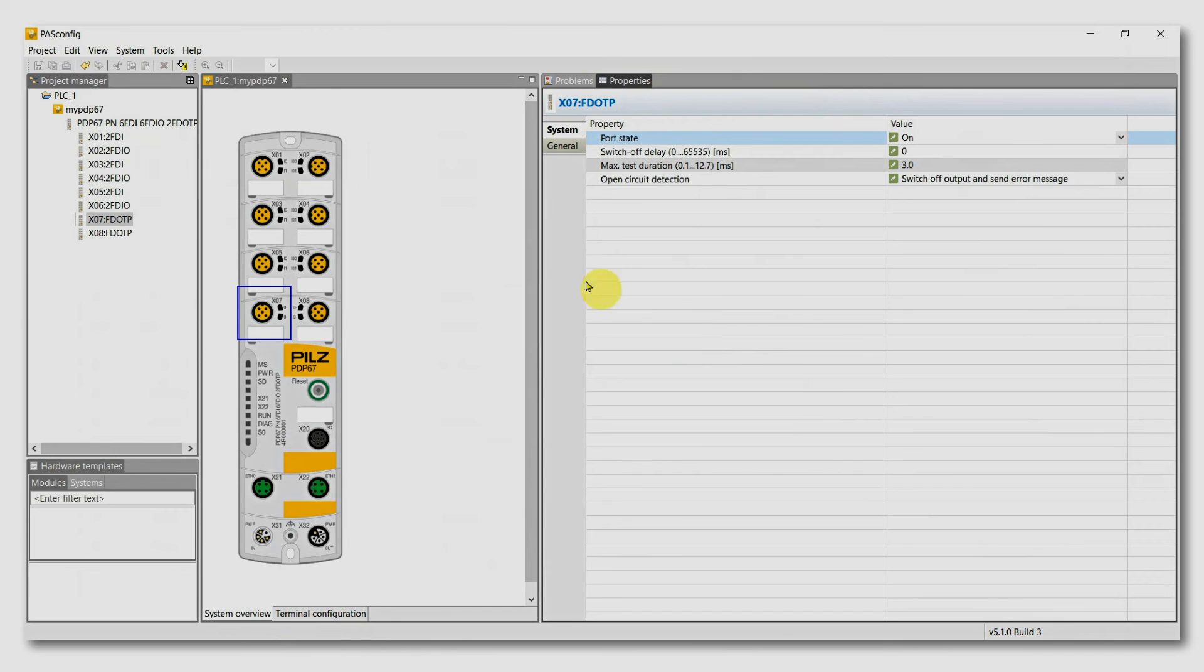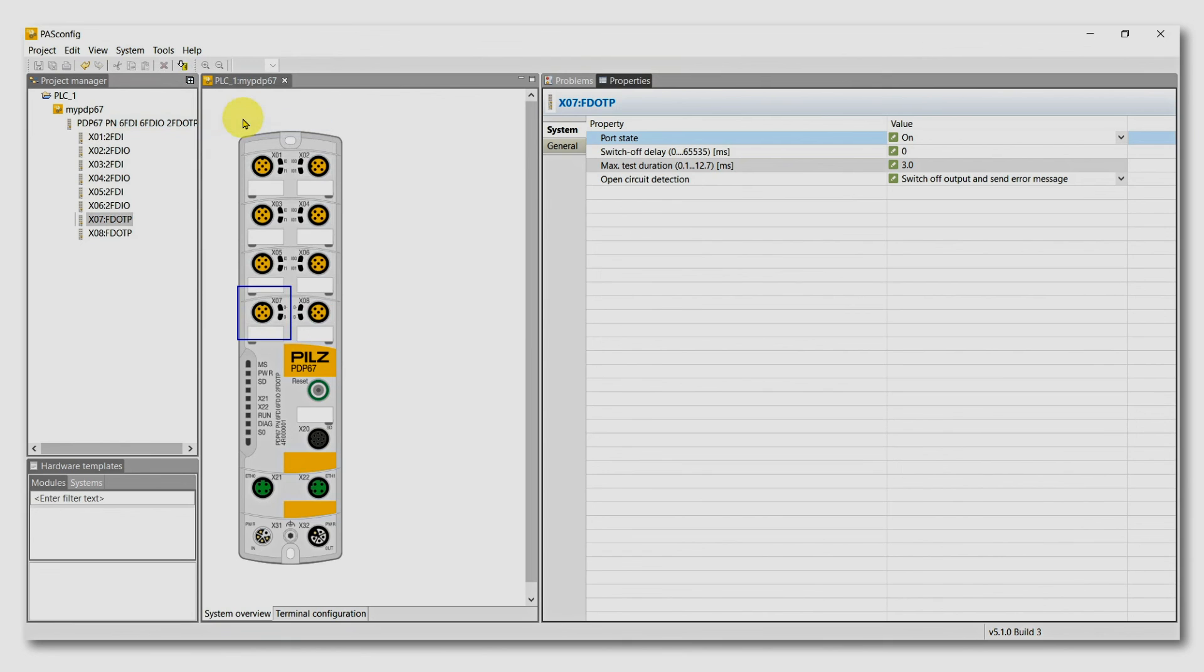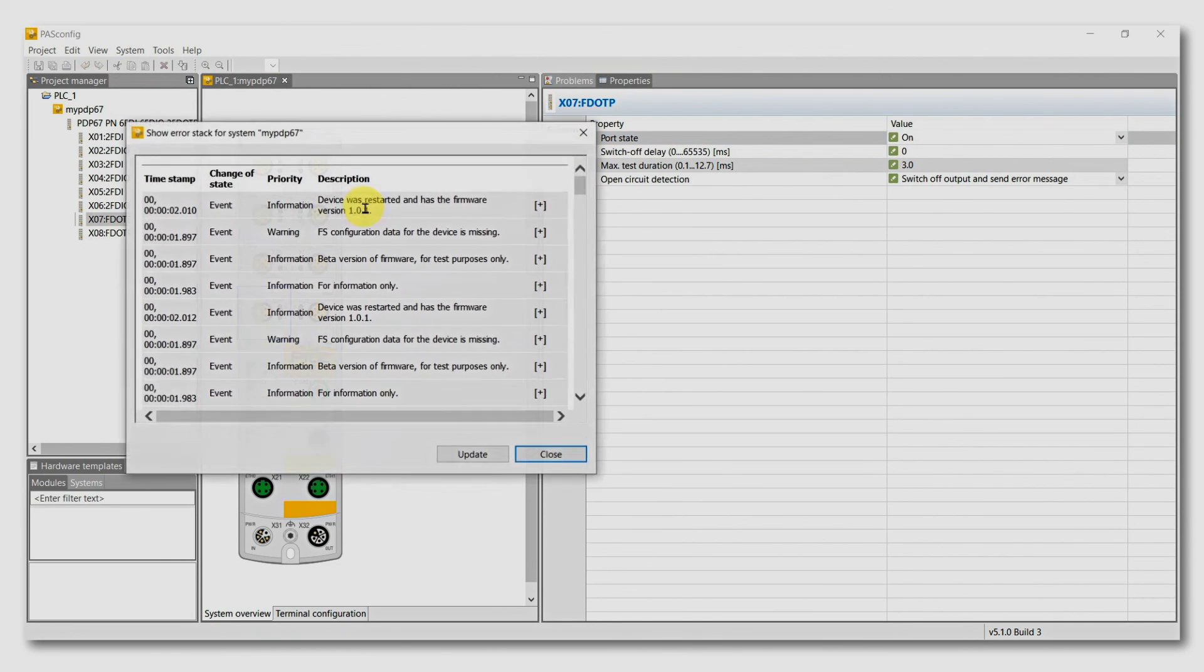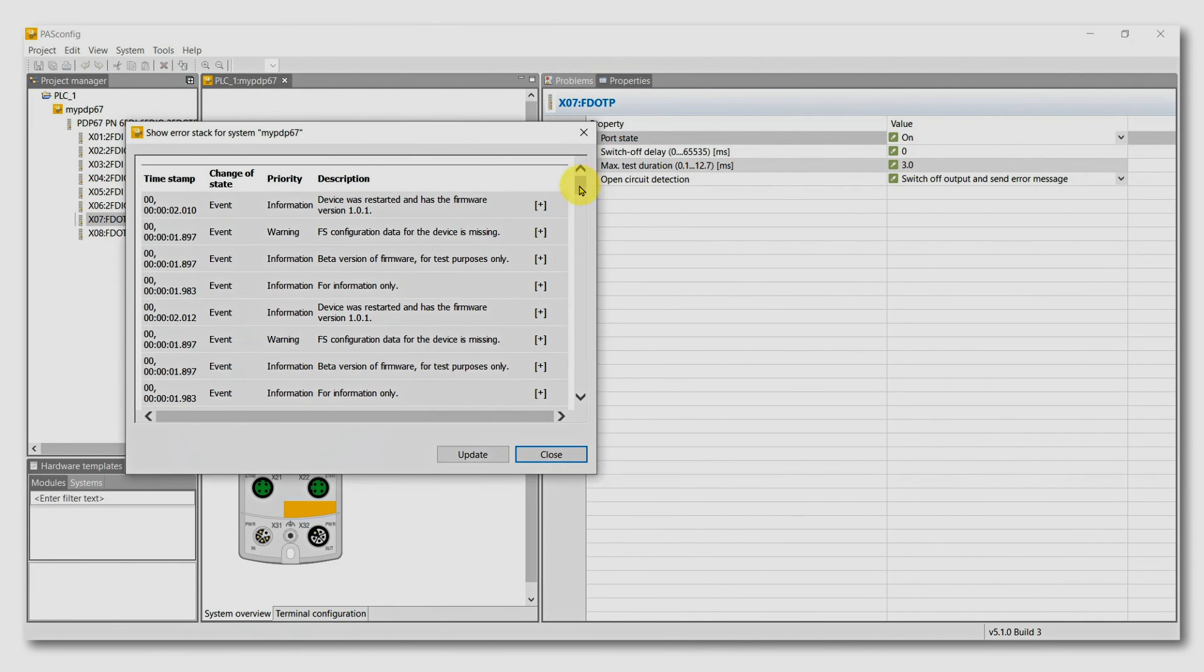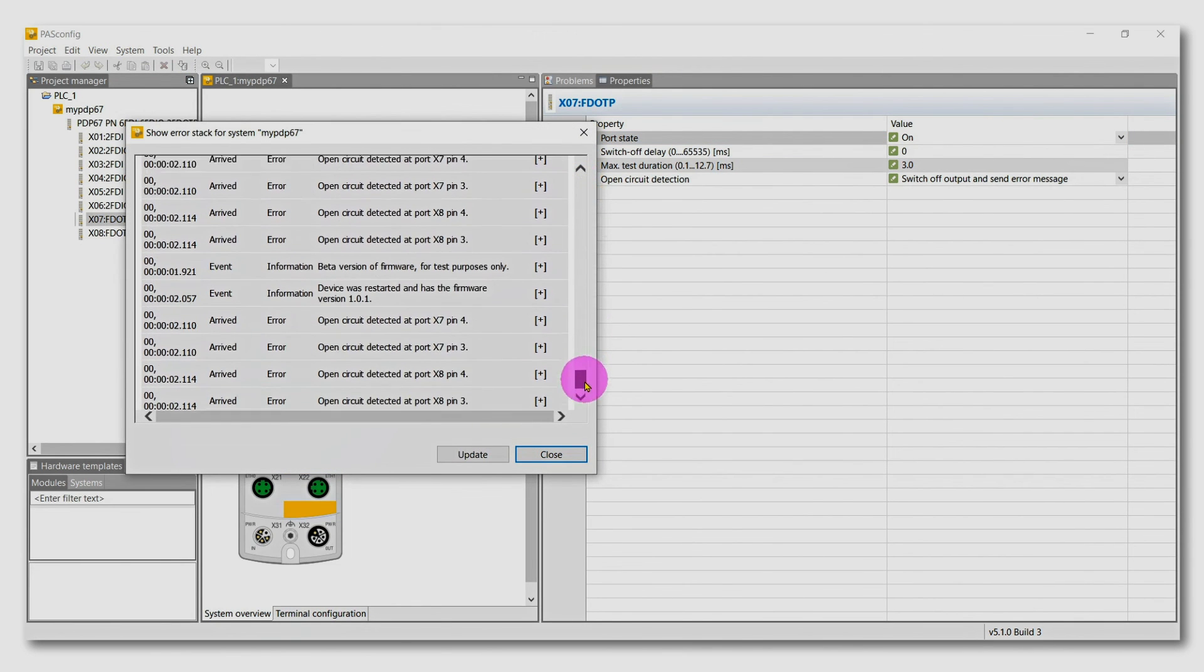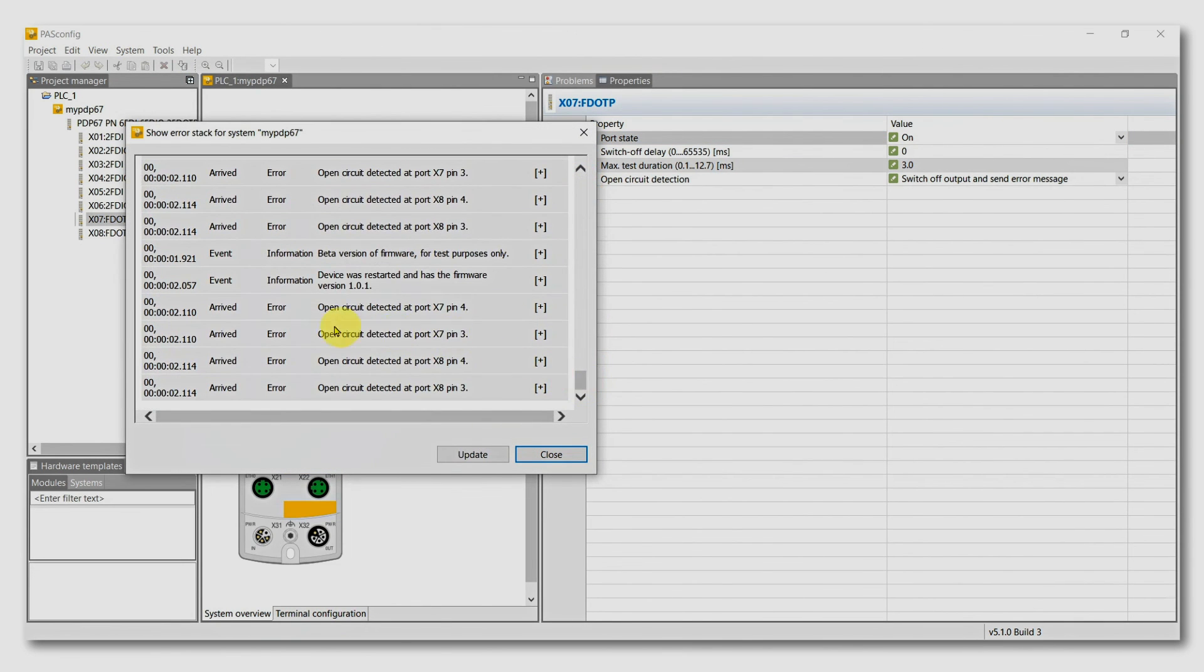The error stack can be displayed or saved to a file via the menu System Show Error Stack or Export Error Stack. Now let's show the error stack and the newest entry is at the bottom. You see an open circuit is detected because we have configured switch off and send an error message.